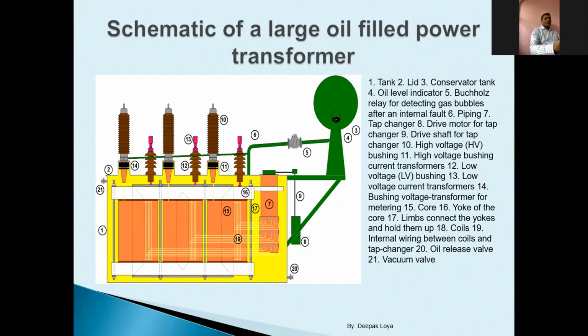For example, the transformer shown in the picture is a step down transformer, which is stepping down the voltage from 765 kV to 132 kV. So what will be my LV side? LV side will be 132 kV. What will be my HV side? HV side will be 765 kV. So depending upon the mandatory line to ground clearances required, the height of the bushing is decided. So there will be HV bushings and there will be LV bushings. The LV bushings will be shorter in length, and the HV bushings will be taller.